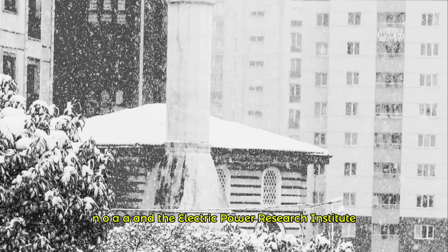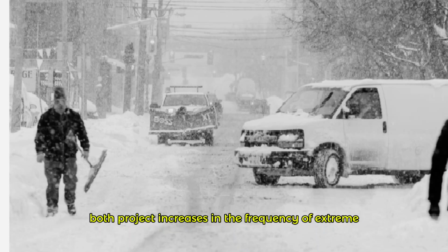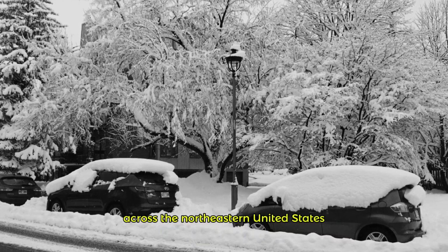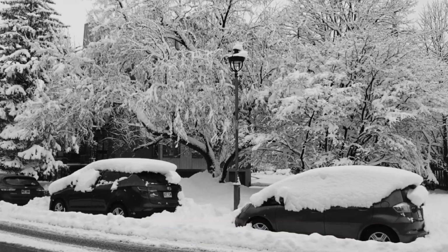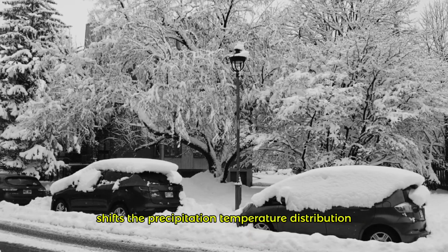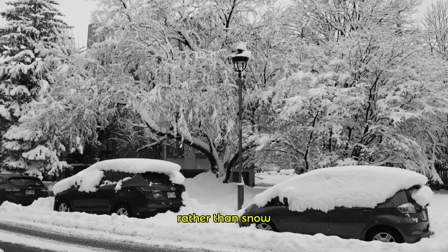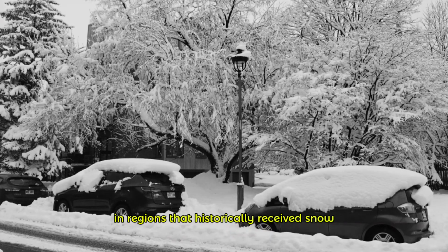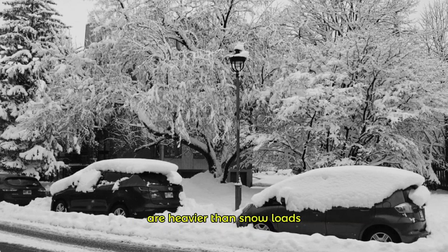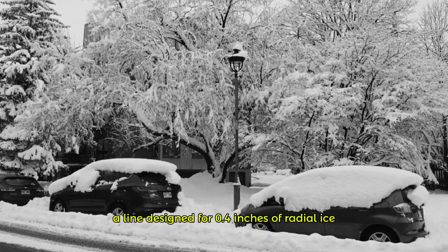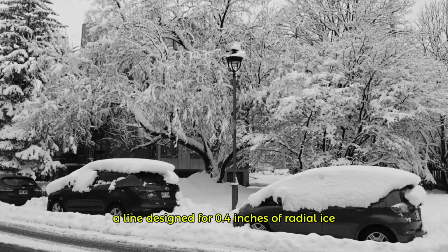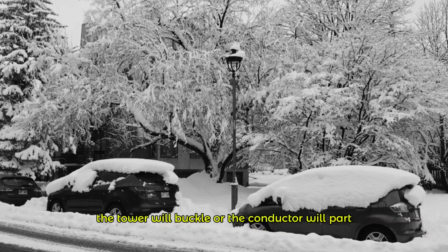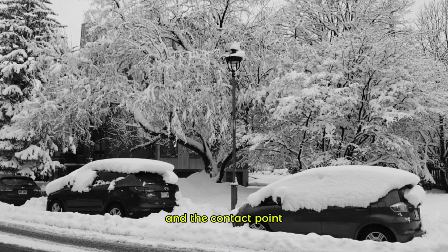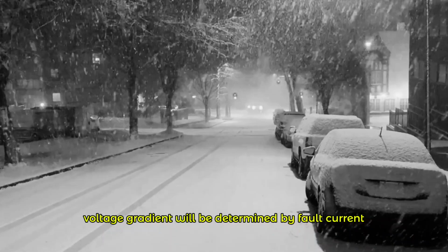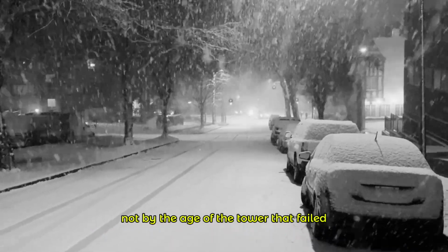NOAA and the Electric Power Research Institute both project increases in the frequency of extreme precipitation events, including freezing rain events at the severity of the 1998 storm across the northeastern United States through the coming decades. Warming shifts the precipitation temperature distribution toward the range that produces freezing rain rather than snow in regions that historically received snow. Freezing rain loads on conductors are heavier than snow loads for equivalent precipitation. A line designed for 0.4 inches of radial ice that sees 1.5 inches will fail. The tower will buckle or the conductor will part, and the contact point voltage gradient will be determined by fault current magnitude and soil conditions, not by the age of the tower that failed.